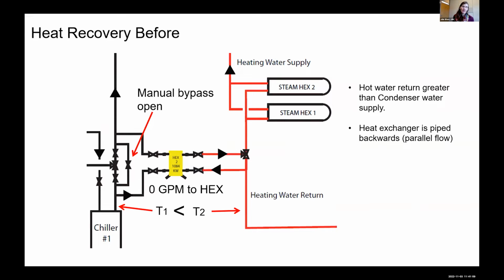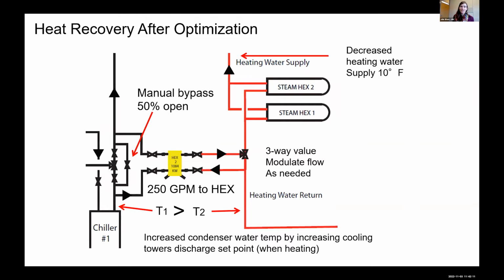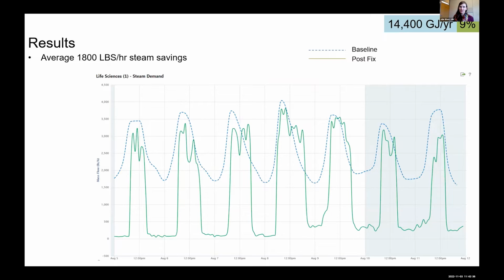And then the second was temperature. The temperature of the condenser water loop was less than the heating water return temperature, so it's just not possible to actually inject heat into the heating system. What was done is that we decreased the heating water supply set point, which then decreased the return set point to a level that we could actually reject heat into it, and then closed the bypass valve slightly so that it forced flow through the heat exchanger. The results were pretty substantial. This shows the baseline case before the change in the dotted line, and then post after the change in the green line. You see fairly substantial savings in steam reduction, roughly 1,800 pounds per hour, or roughly 14,000 gigajoules per year, 9% of the building's energy consumption.